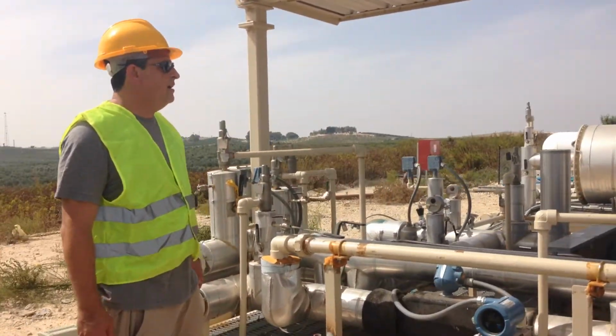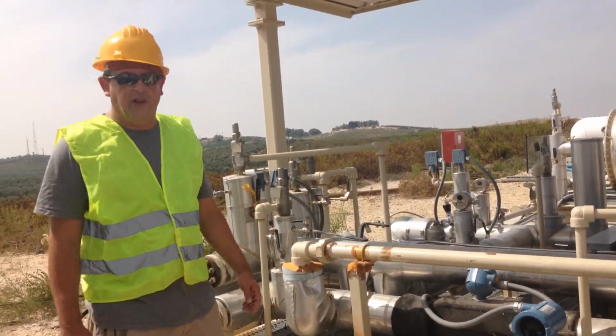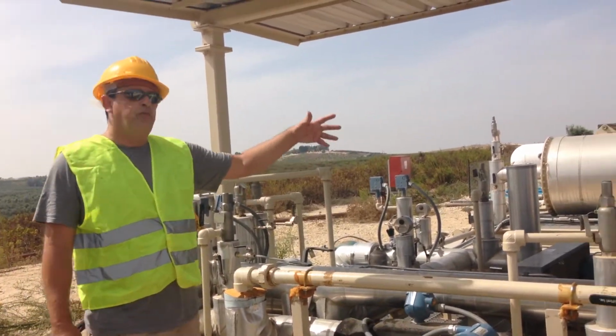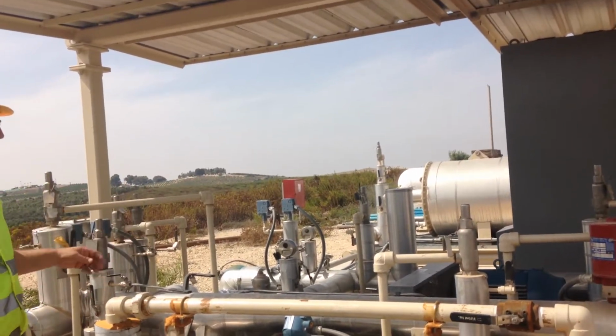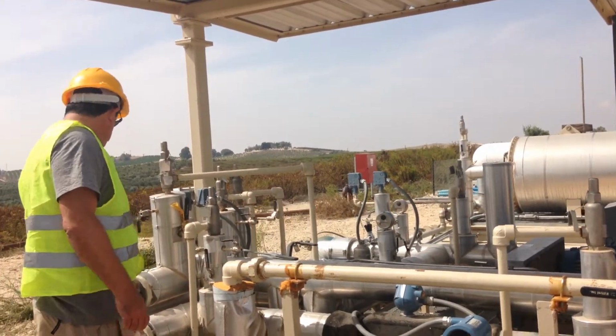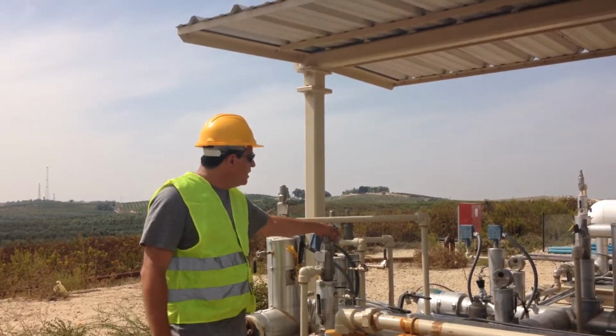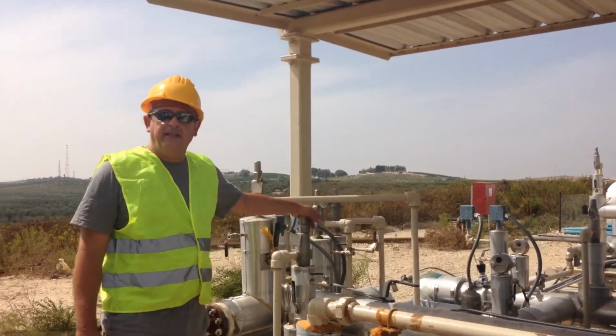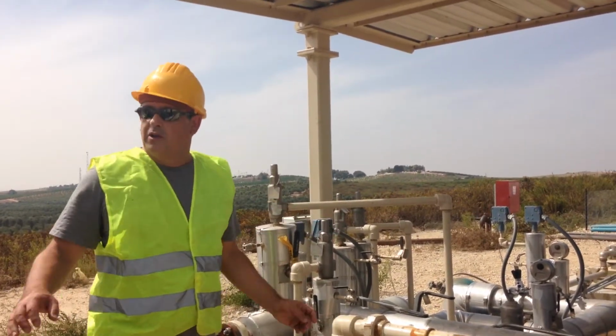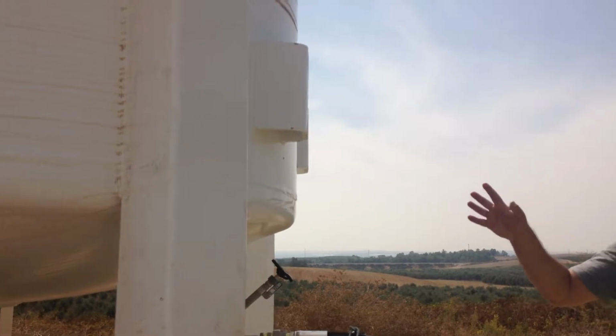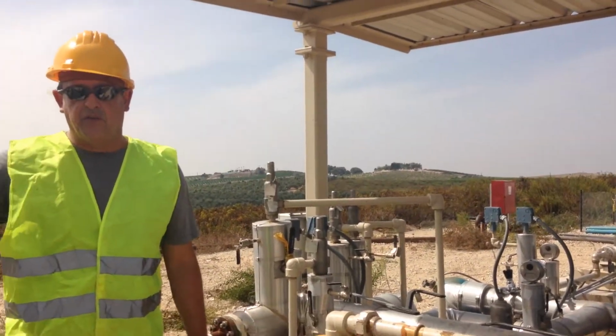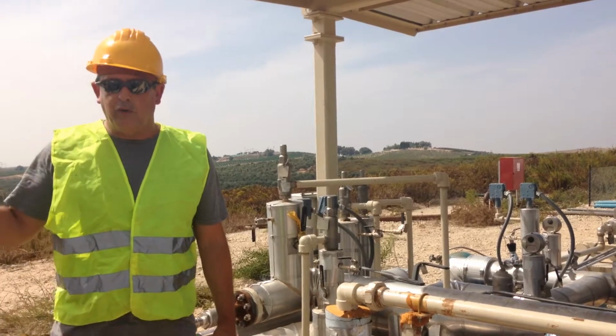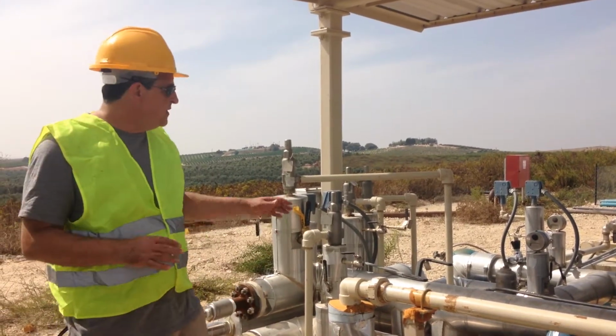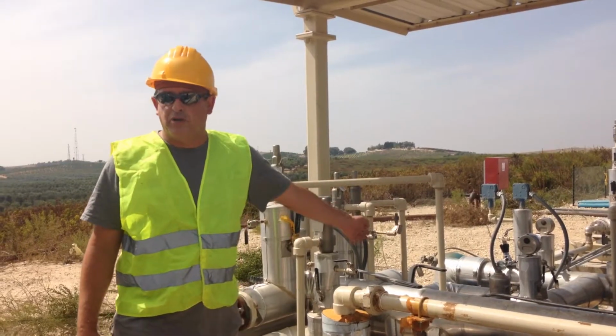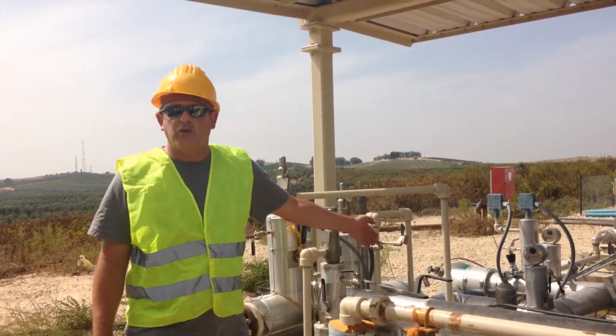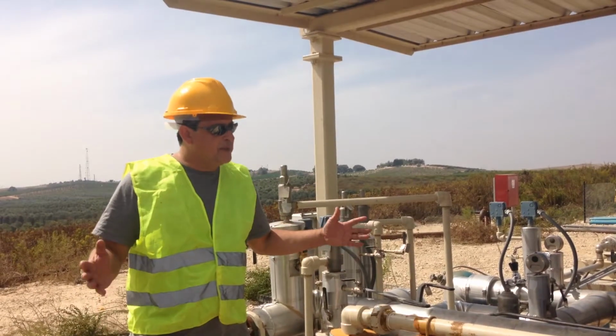The skid is quite a complex system that includes a booster pump and 2 pumps, a low flow pump and a high flow pump, and I will explain what is the purpose of these pumps. Basically the CO2 gets into the system here, and it will encounter first a booster pump that is aimed to increase the pressure of the CO2. The pressure of the CO2 in the tank is 20 bars and the temperature minus 20 degrees Celsius. So it is in liquid conditions, and we want to keep it this way. So this is why the first thing that we do is increase the pressure of the CO2 in the system. Then we make sure that it is liquid, because if it becomes gas, then the system may not work as well.